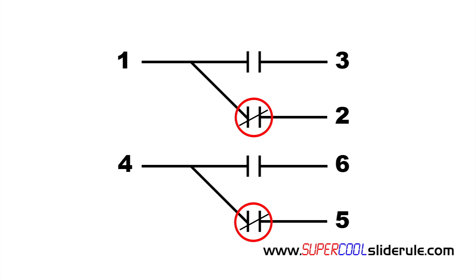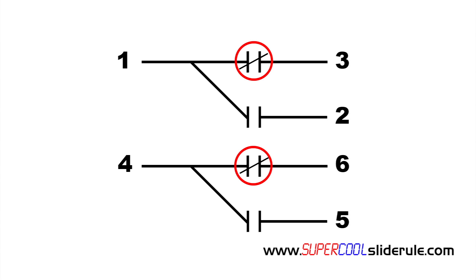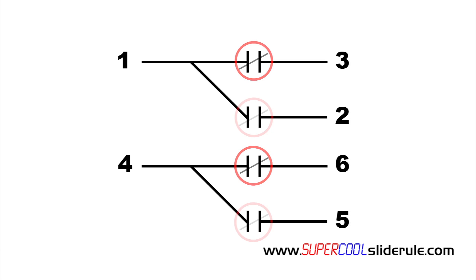Once you supply low voltage to the coil, these two contacts lose continuity with terminals 1 and 4 respectively, and these two should now have continuity with terminals 1 and 4. Once the low voltage is interrupted, the contacts should return to the normal position.